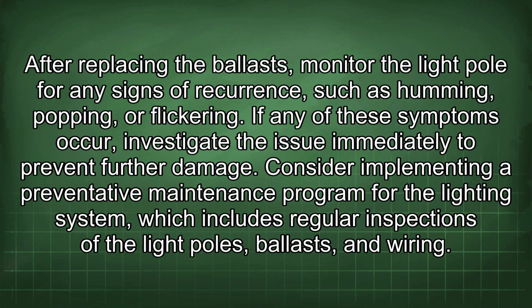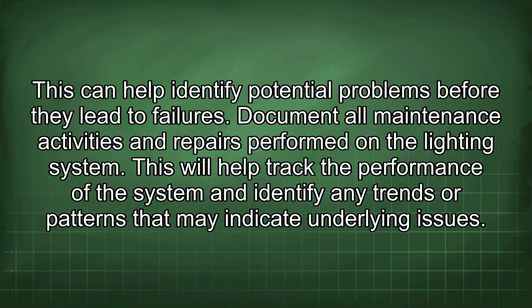After replacing the ballast, monitor the light pole for any signs of recurrence, such as humming, popping, or flickering. If any of these symptoms occur, investigate the issue immediately to prevent further damage. Consider implementing a preventative maintenance program for the lighting system, which includes regular inspections of the light poles, ballast, and wiring. This can help identify potential problems before they lead to failures.